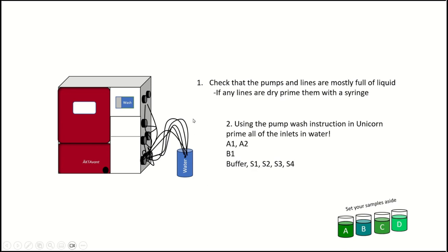It helps a lot to check the waste of the system as it's priming. So that way you can be sure that at least for each pump that you're running, so when you first start running A1, make sure that not only is the inlet line not totally full of air, but that what you're getting out of the back of the system is actually running water, right?